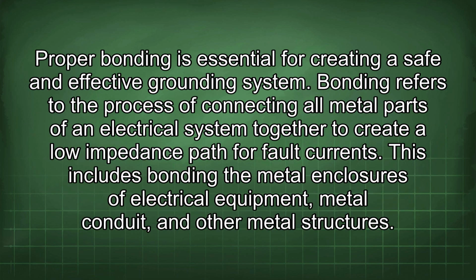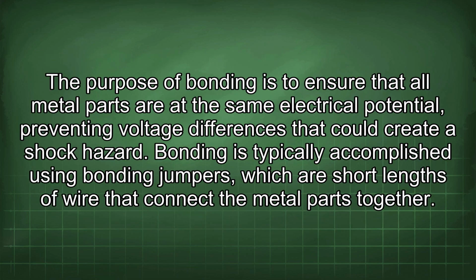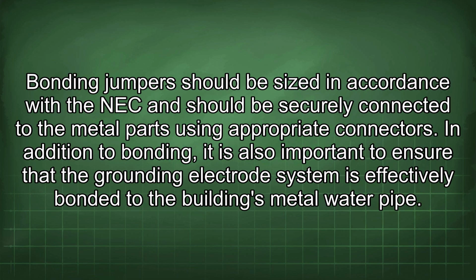Proper bonding is essential for creating a safe and effective grounding system. Bonding refers to the process of connecting all metal parts of an electrical system together to create a low impedance path for fault currents. This includes bonding the metal enclosures of electrical equipment, metal conduit, and other metal structures. The purpose of bonding is to ensure that all metal parts are at the same electrical potential, preventing voltage differences that could create a shock hazard. Bonding is typically accomplished using bonding jumpers, which are short lengths of wire that connect the metal parts together.